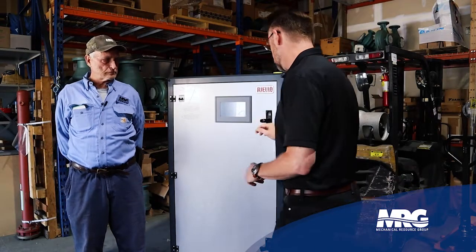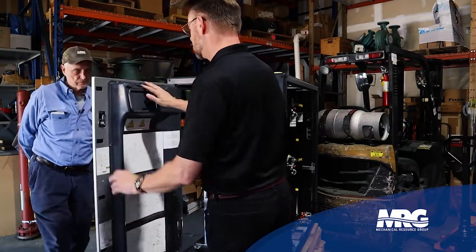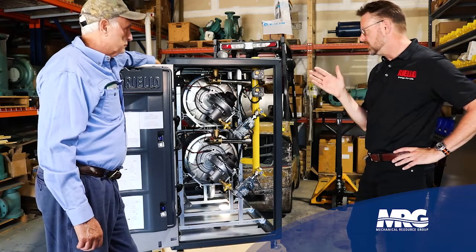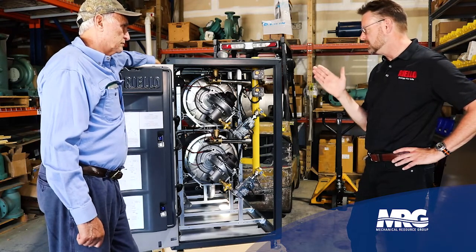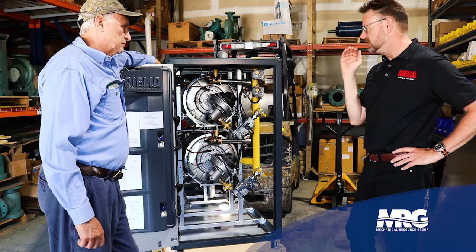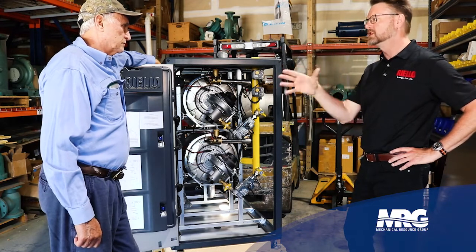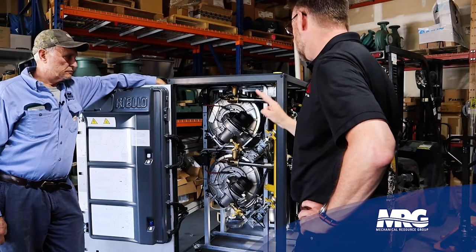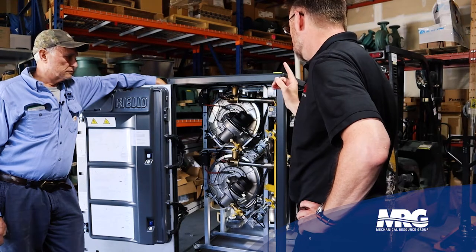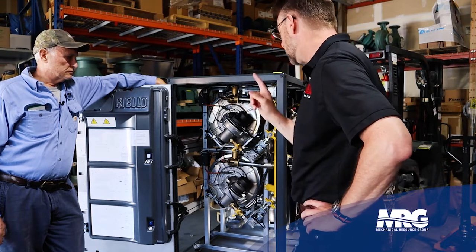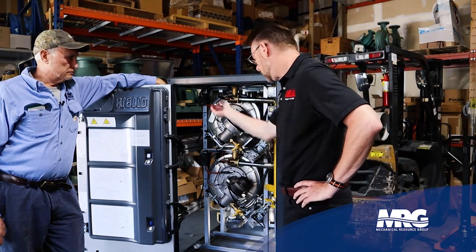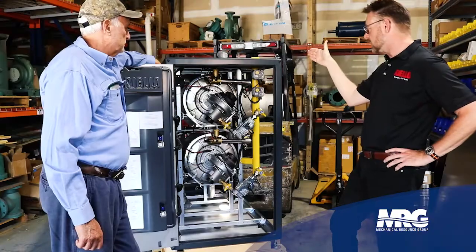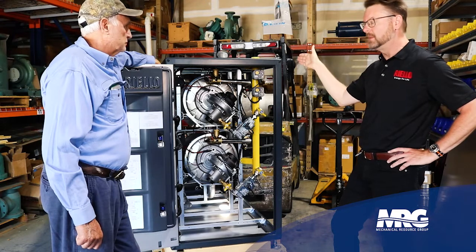Okay, if we could, you can jump in front of the door here, Tommy. Tommy, good news. Now, when you had the low water cutoff failure on that particular boiler fired heat exchanger, you went from having some heat available to how much heat available? 0. 0 heat available, okay. Riello Array, redundant low water cutoffs. Now, we're going to have an opportunity to have that low water cutoff challenge here, or here. These are independent low water cutoff probes. There is a low water cutoff that exists back on the common manifold.